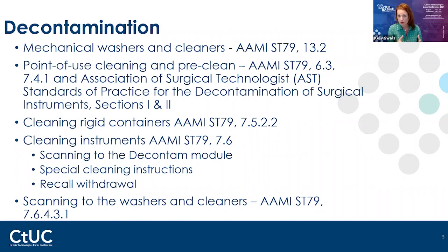Along with that, with your washers, where I said it should be tested each day that it's used, I'm still seeing weekly testing. That did change in 2017, where they went from weekly to daily. So I highly recommend that everyone is doing that wash test daily and that it is for all your washers, whether it's an ultrasonic, a mechanical washer, a cart washer, everything should be tested. And I can speak from experience, years ago when we were doing just weekly testing.